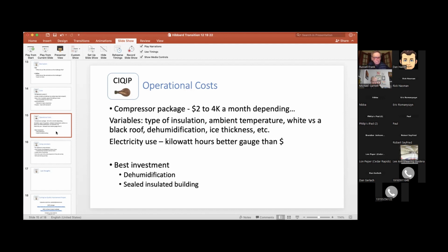Your ice depth has a big impact on the cost of your operation. Your ice temperature, indoor air temperature—if you run 42 degrees, it could save you $200 to $500 a month just on maintaining your ice temperature. Your insulation in the building and ambient temperature affect your energy costs, because the warmer it is out, the higher the condensing temperatures, the tougher it is to get rid of that heat. Basically, when you're refrigerating your floor, you're extracting heat from the floor and disposing of it outdoors. If it's 50 degrees out, the chiller's laughing. If it's 100 degrees, it's gagging because it's working like heck.